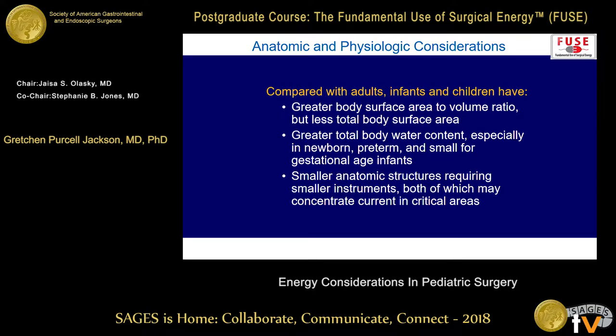Compared with adults, infants and children have a greater body surface area to volume ratio but less total body surface area — meaning less real estate for your operative site, monitoring devices, and dispersive electrode. Greater surface area to volume ratio also means areas of high resistance are in close proximity to areas of low resistance, so the path and behavior of current may be much less predictable than in adults.